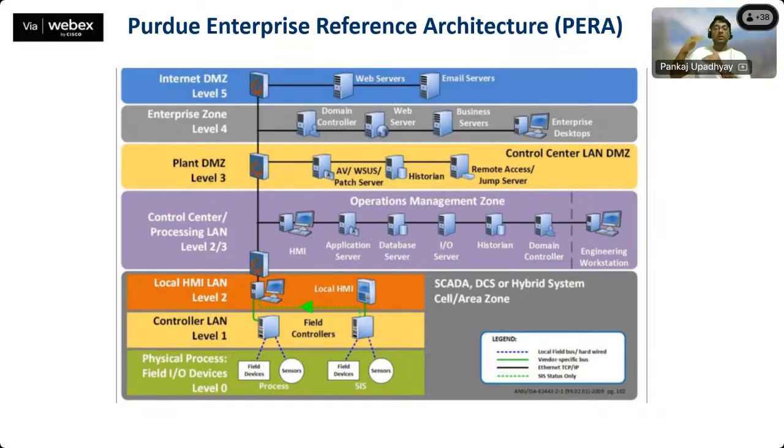So we have to minimize the attack surface by network segmentation. That's why in OT we have the Purdue Enterprise Reference Architecture to follow. But most organizations' OT doesn't follow it. Now, as they adapt towards cybersecurity and see how cyber threats can impact their operations, they are implementing and refining their network architecture as per Purdue.